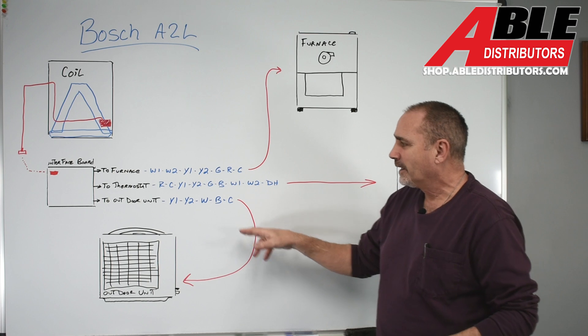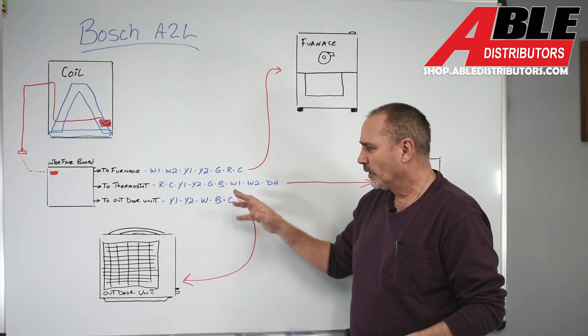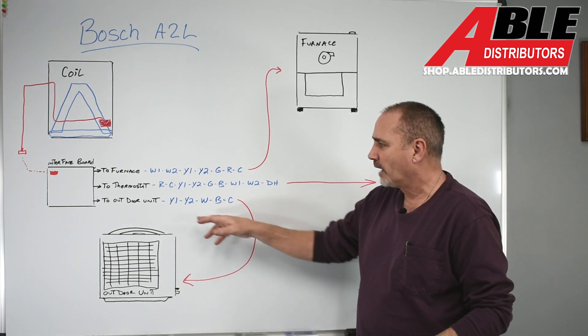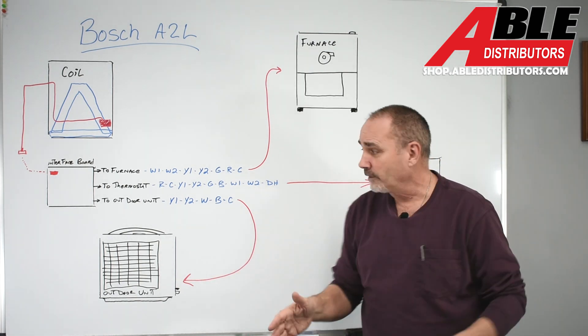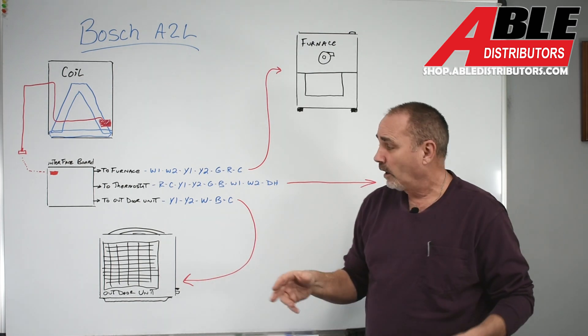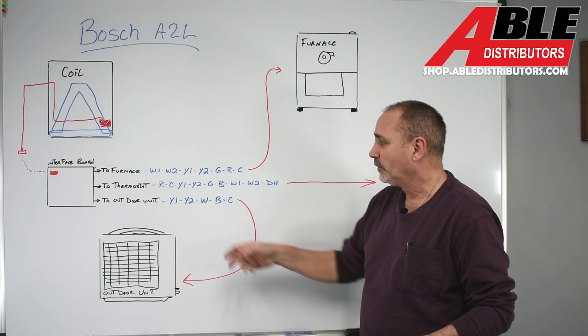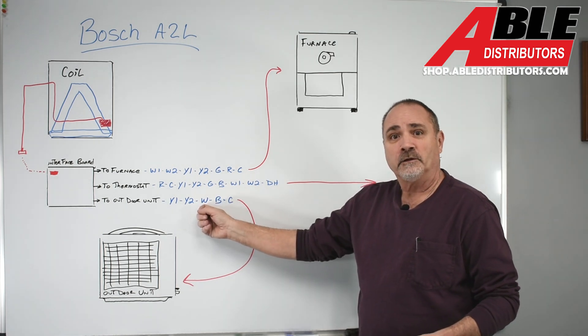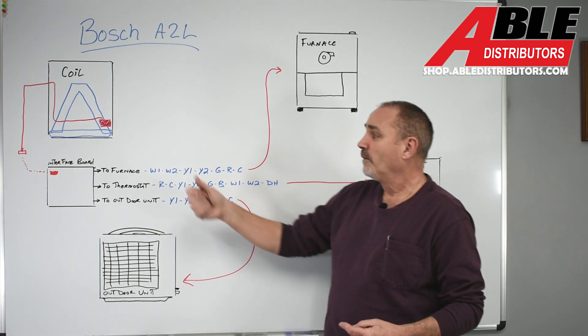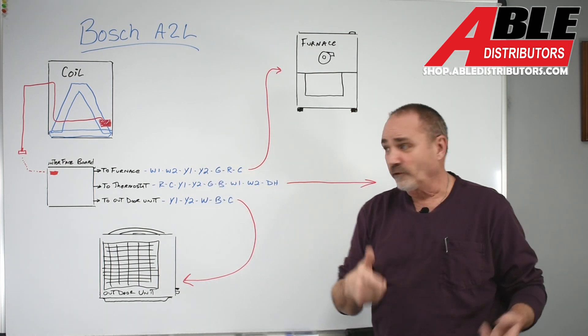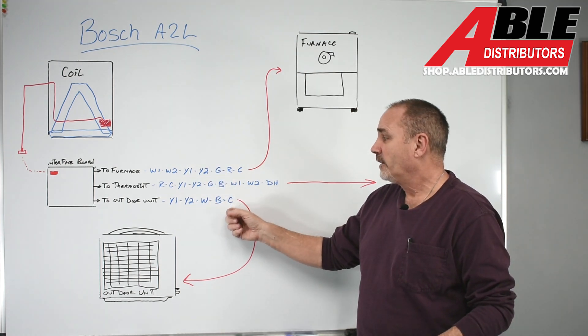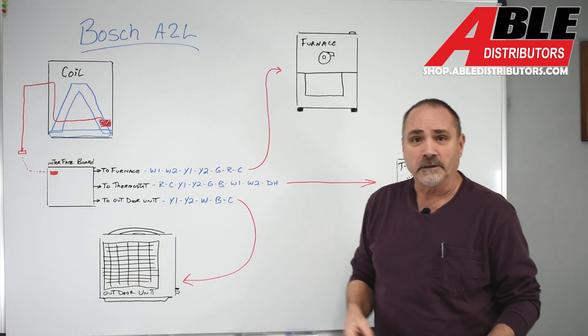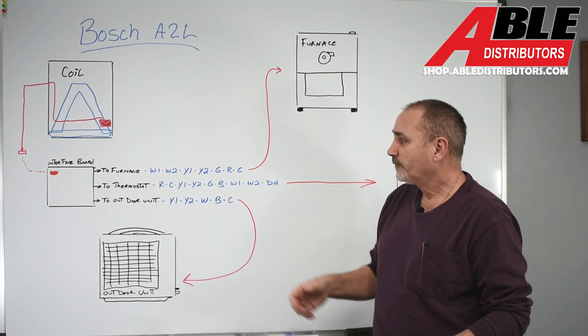And then going to the outdoor unit, again, they don't know what you're doing here. It's a generic box. So you got Y1 and Y2, again with the Bosch, not going to matter. It's only a Y call. So whatever you hook up here, just make sure you carry it through. The W, you'll need that because that'll send power back to the furnace for defrost. The B, reversing valve, and the common for your Y, I mean, and your reversing valve. So that's it.